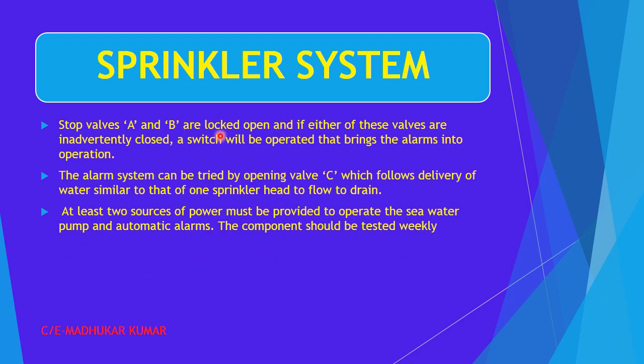The stop valves A and B, which we have seen in the main diagram, are locked open, and if either of these valves is inadvertently closed, a switch will be operated that brings the alarm into operation. That means that when they are closed, the arrangement is such that it will give an alarm on the bridge. The alarm system can be tried by opening valve C, which allows water, similar to the delivery of one sprinkler head, to flow to the drain. So when we have to try out the alarm, this test alarm valve, that is C, is to be operated.